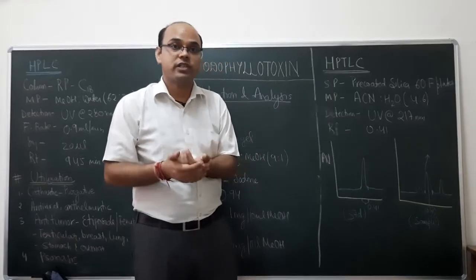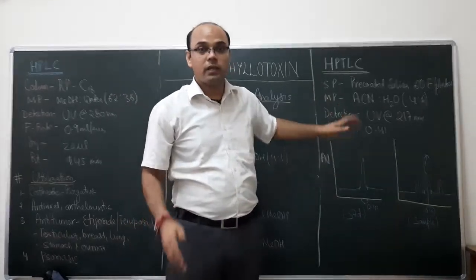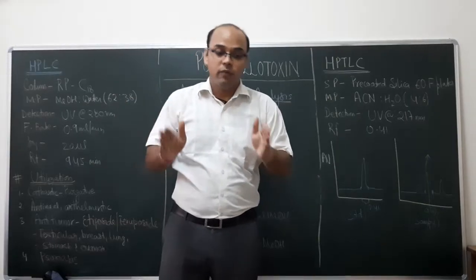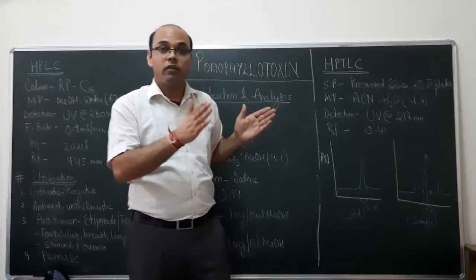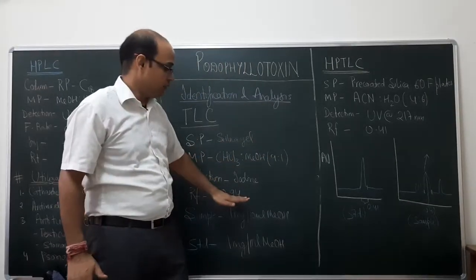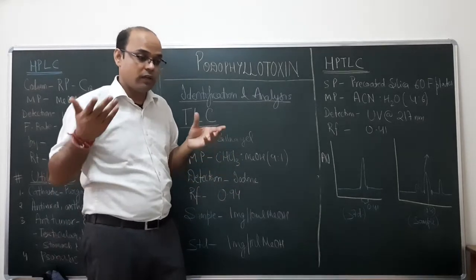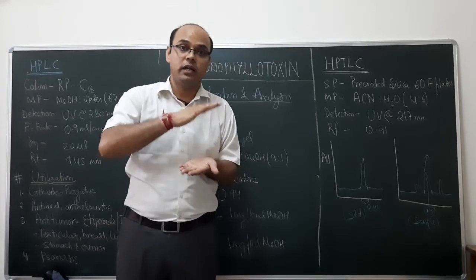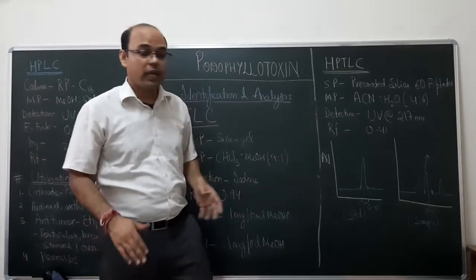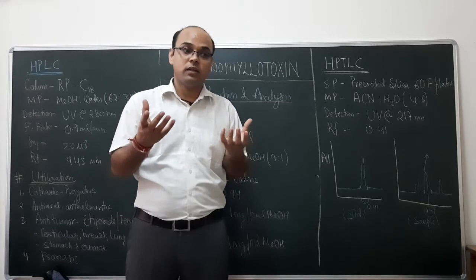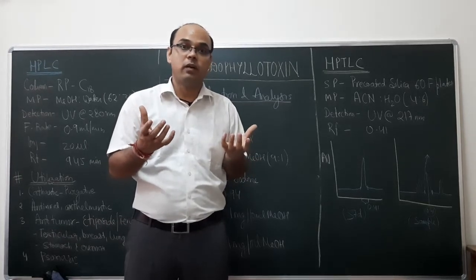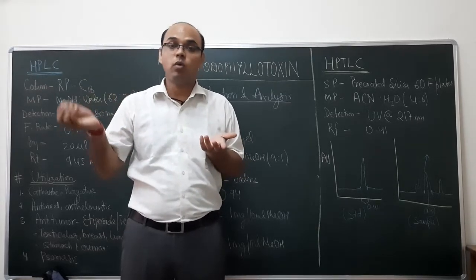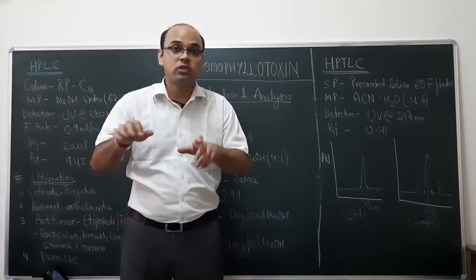In the same way it applies the standard. After application of the sample, the plates are dried in a special chamber, and after drying we use a development chamber. In TLC we pour the solvent into a development chamber and keep it under closed conditions. But in HPTLC we have an automatic development chamber, where the machine itself adds the amount of solvent which you have entered into the software.